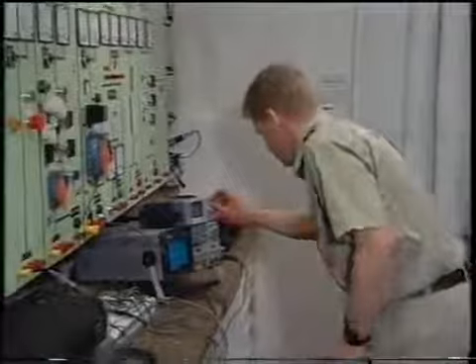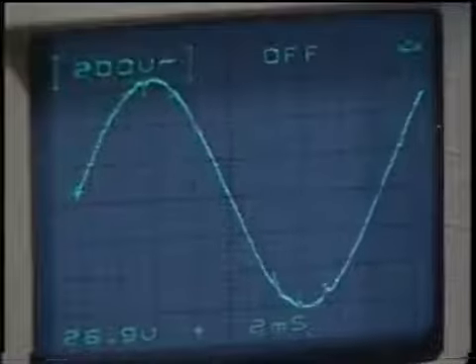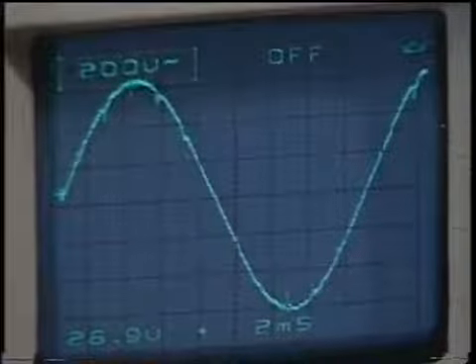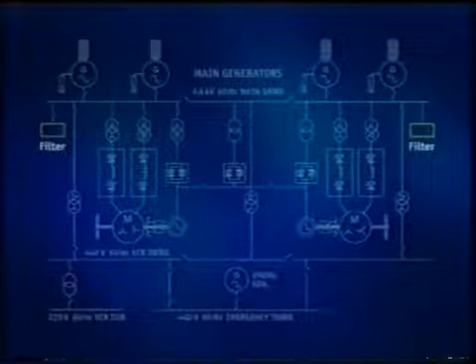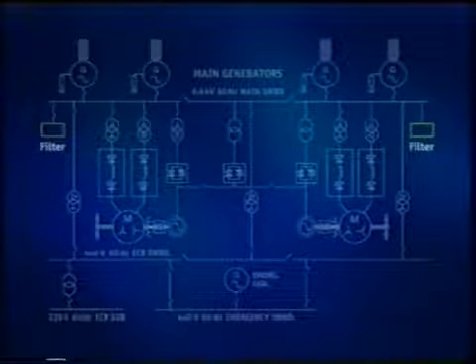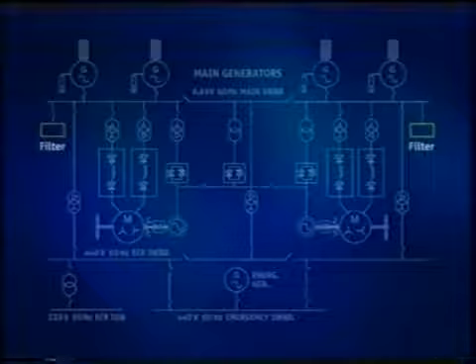Here we see the AC supply voltage has harmonic disturbance, showing as small spikes on the sinusoidal waveform. This is because the propulsion is running without harmonic filters, which have tripped out due to a fault. The harmonic filters are circuits with very low impedances, which are tuned to the troublesome harmonic frequencies. The filter action is to absorb unwanted harmonic currents caused by converter switching.